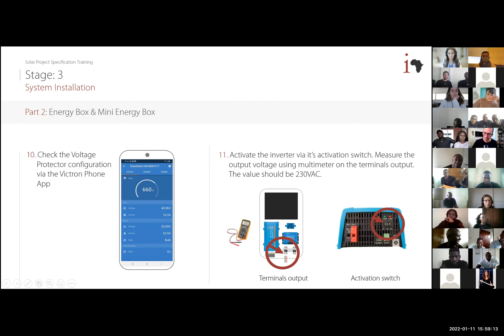Now, when all the components inside the energy box are checked except one, the cellular modem, the last thing to check is on the door - the battery monitor screen. If it's functioning, you'll see it on, showing the status of the battery and the percentage it is charged. When we send batteries to Africa, we charge them to 30% only, due to limitations on shipping them by airplane or boat, so you'll expect to see this value, plus or minus. If not, you can check with the Victron phone application that the battery is charging and that the value rises accordingly. So you check the monitor screen.